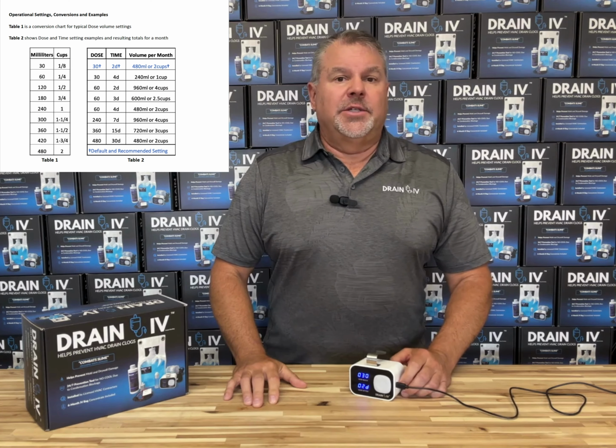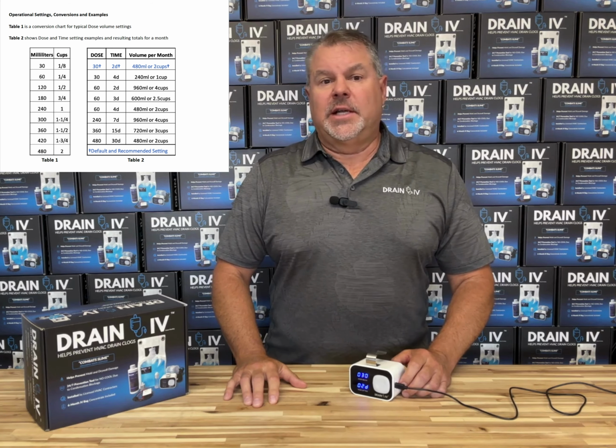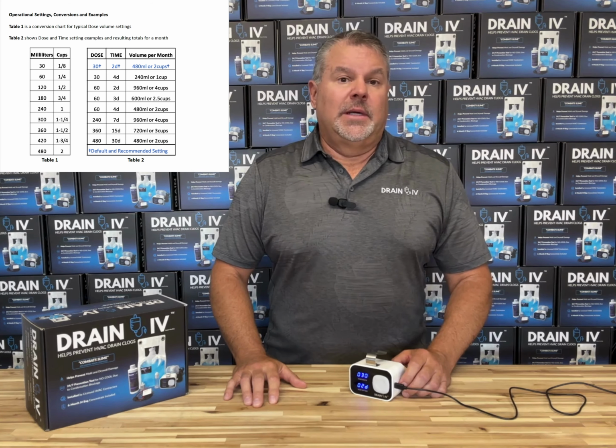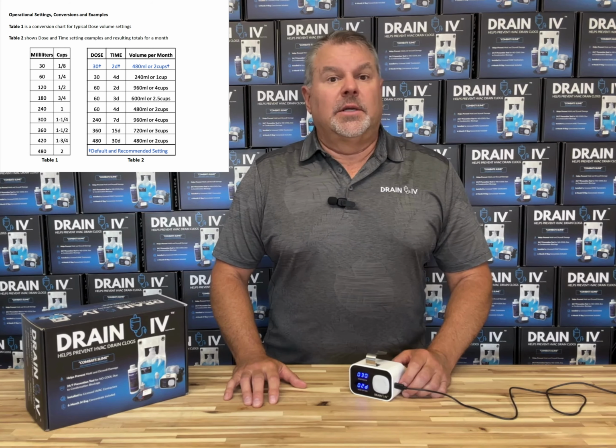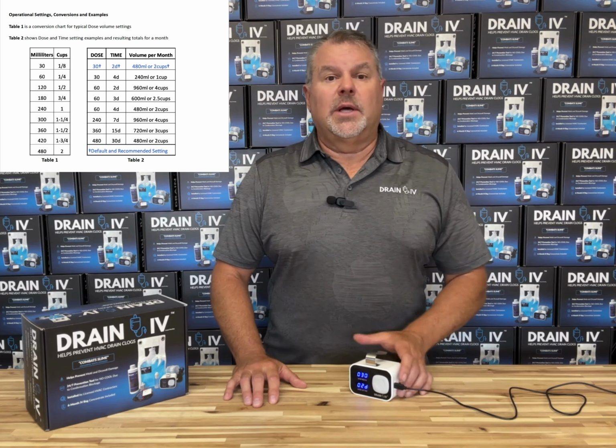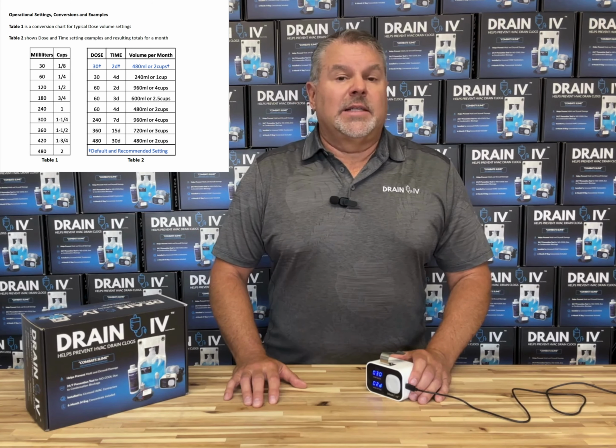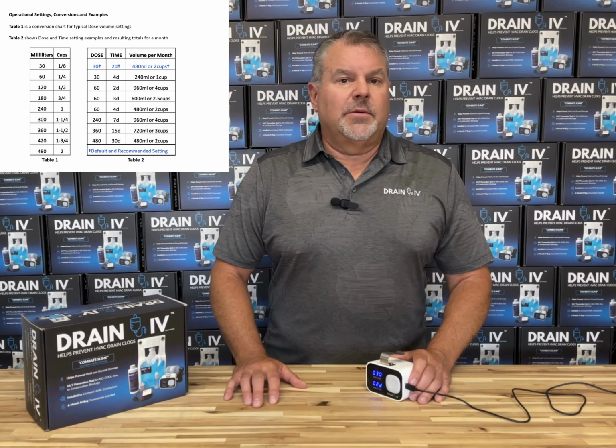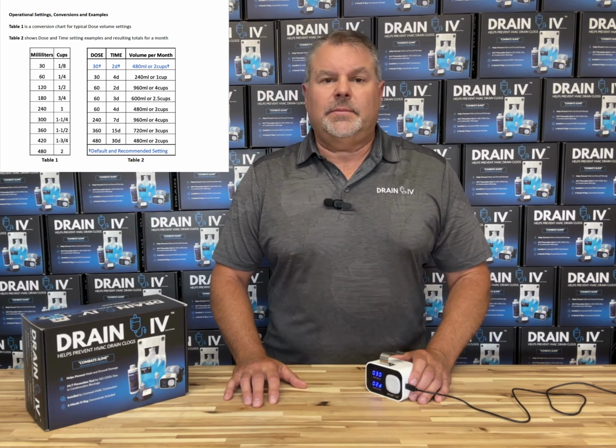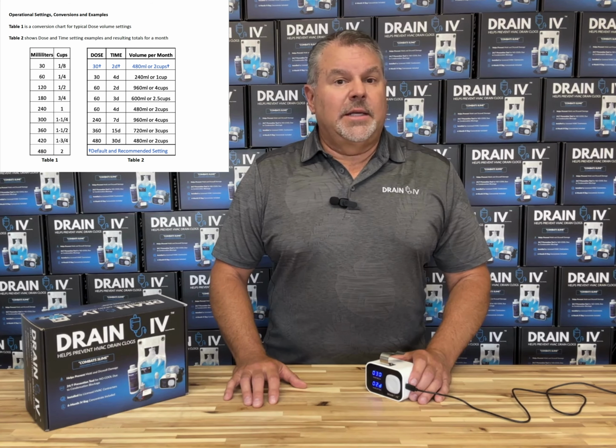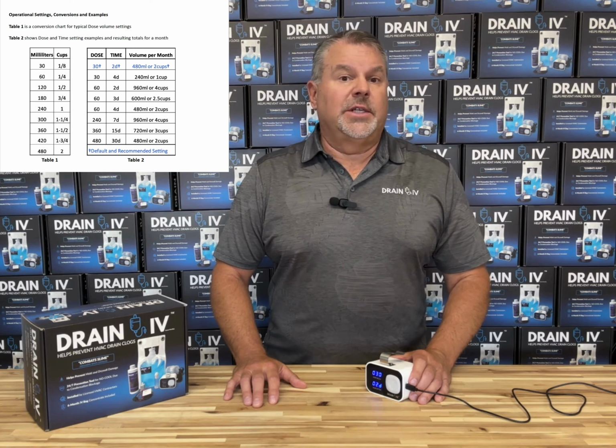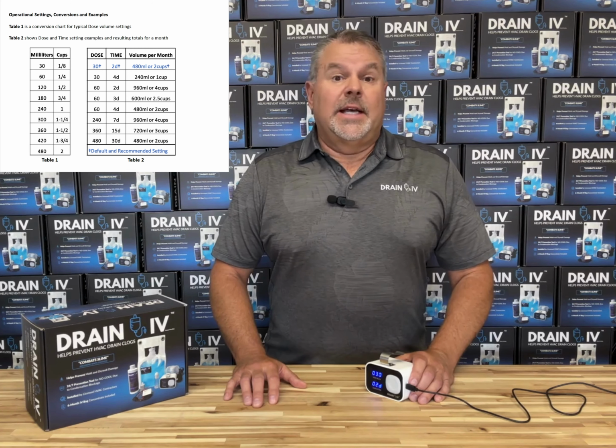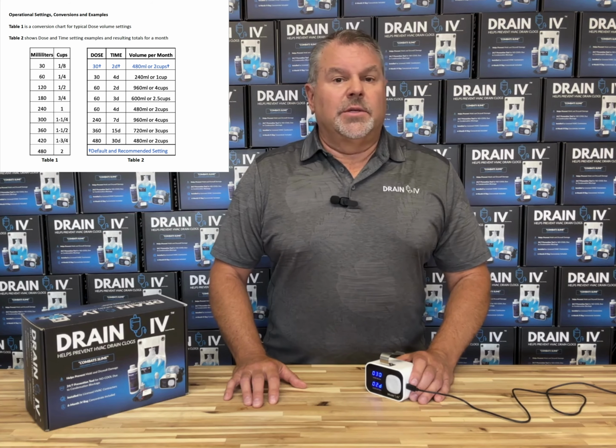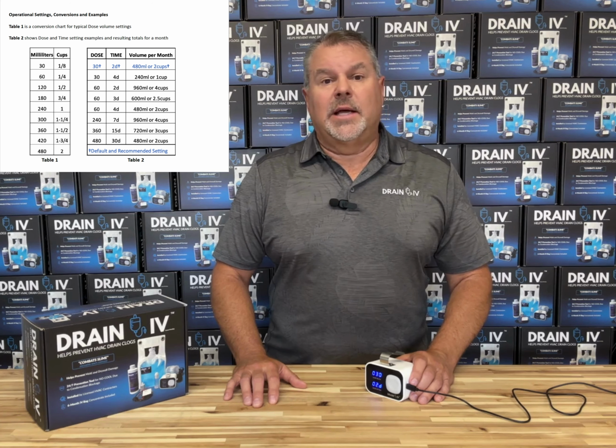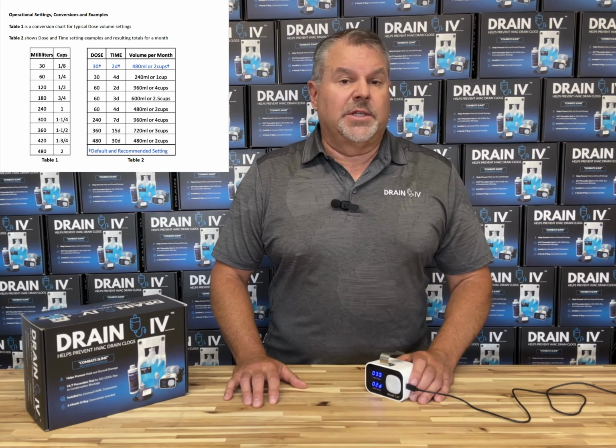The instruction has a table that shows milliliters to cups conversions and examples of different settings with a total delivered per month. At the default settings of 30 milliliters or 1/8 of a cup every 2 days, a total of 2 cups will be used each month, and the IV bag will last about 8 months. We recommend that you use a 6-month interval to refill your IV bag at your client's biannual service to make sure that it doesn't go empty. Note that if you increase the dose or time settings to deliver more than 2 cups a month, you may have to adjust your servicing timing. For example, settings at 60 milliliters or 1/4 cup every 3 days will use a total of 2.5 cups per month, and the IV bag will last 6.4 months, cutting it close for servicing every 6 months.